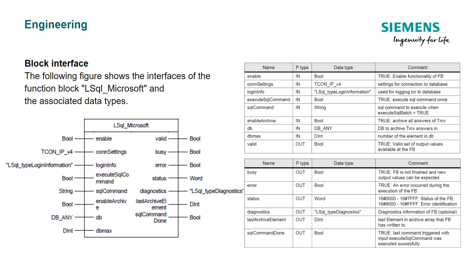Here is an example of the overall block interface. The following figure shows the interfaces of the function block LSQL Microsoft and the associated data types, broken up into two tables on the right covering ins and outs. You will want to identify the things that are required, starting with enable, which enables the overall functionality of the function block. Also go through the connection settings, where you will identify the IP address of the server and the port connections. From there, go into the login information — collect this from your IT department or from the build that you did for the MSQL server.